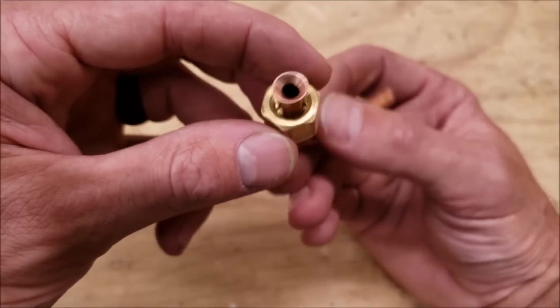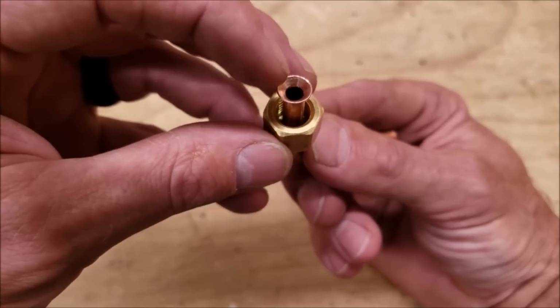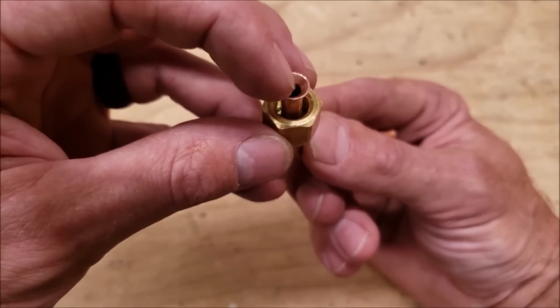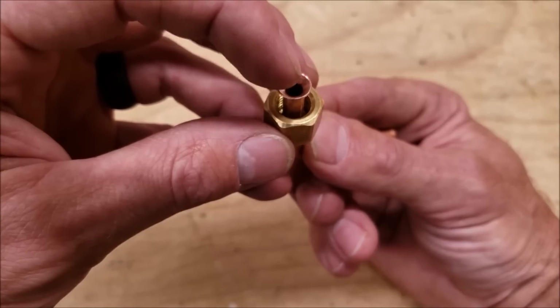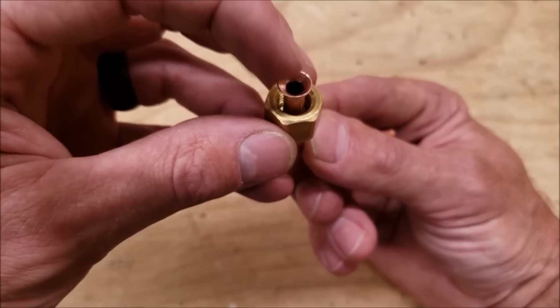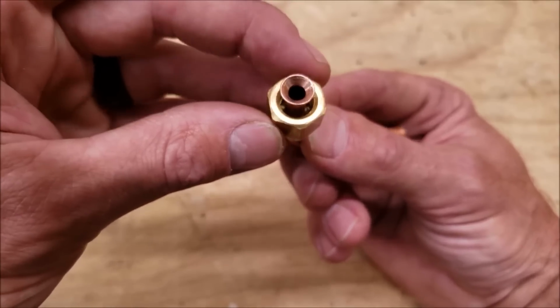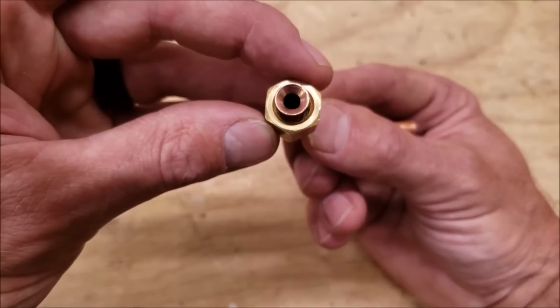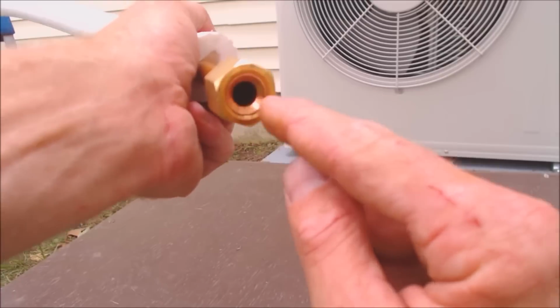Then you slide your nut back again. You can eyeball where the flare goes and connects to the flare face on the flare adapter. Make sure it's covering the entire surface. That's a big deal. A lot of flares that I see, especially pre-made ones, are only halfway made, halfway done. And this with a bad flare nut, you end up cutting it off and making your flare anyway. So you make sure that's all seated right.